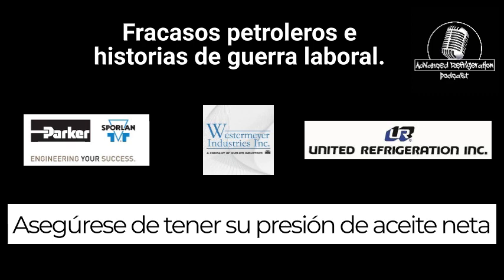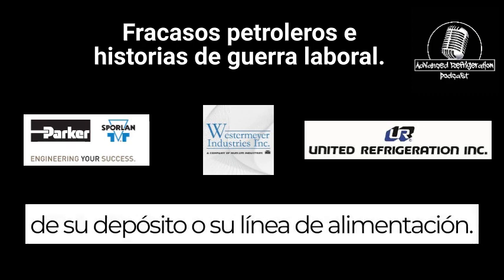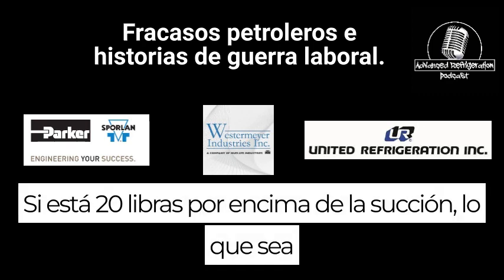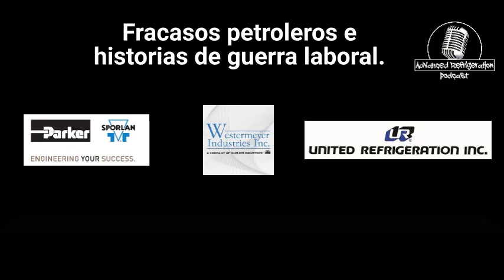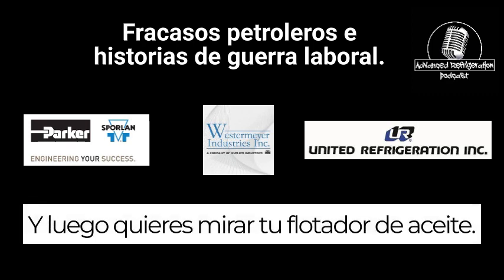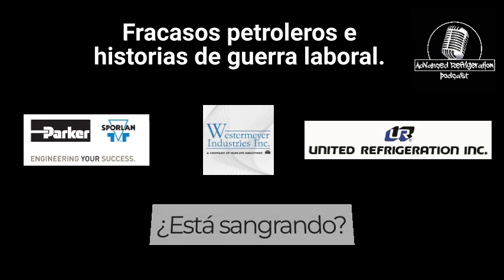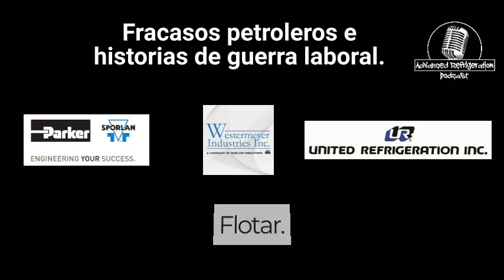Make sure you have your net oil pressure from your reservoir or your feed line. Make sure it's whatever it's supposed to be. If it's 20 pounds above suction, make sure it's at that. Make sure you have full flow. Make sure your oil filter's good. Then look at your oil flow. Feel the crankcase of the compressor. Is it smoking hot? Is it bleeding through? Is that why it's not pushing oil into the flow?